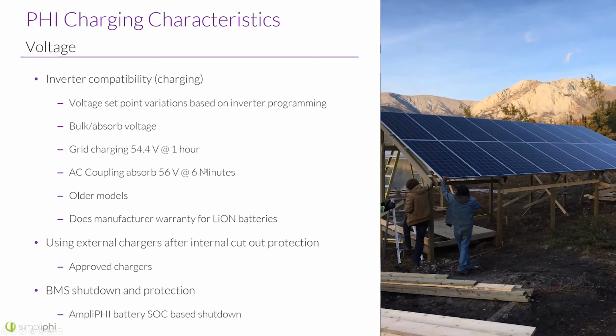Now, when we are grid charging or charging from an AC source such as a generator, or even an AC coupled array, we need to make sure that we do not use float. It doesn't make a lot of sense in that case, and definitely not when we are AC coupled. So this is a 2-stage, no float charge when it comes to charging from an AC source. As far as compatibility with inverters and chargers, if it's an older model, like I mentioned, check for this absorb time. Make sure they warranty for lithium batteries if it is an older model as well.